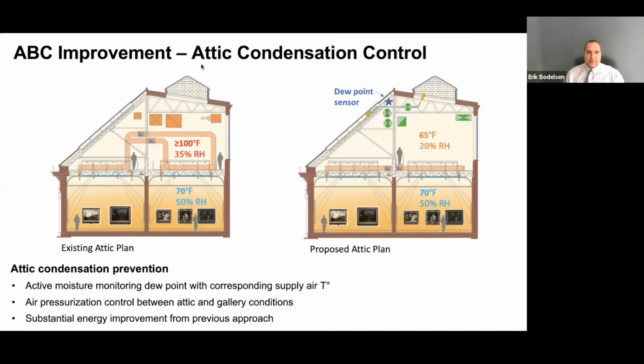The primary means for controlling condensation, as Michael indicated, was through superheating of the attic, generally around 100 degrees. This large temperature discrepancy between the galleries and the attic would compromise the gallery conditions below, and also contributing to the issue were pressure differences in the attic at the boundary, forcing air in some instances up into the attic and in some instances down, that heated air down into the galleries.